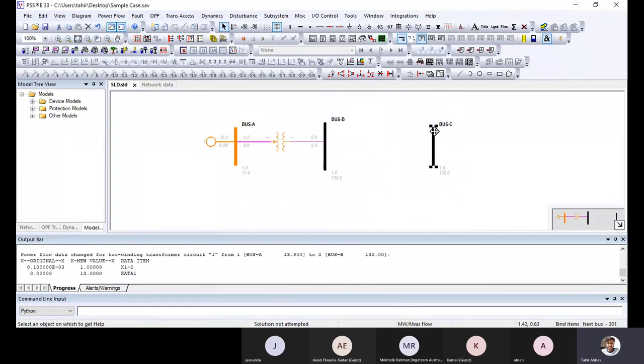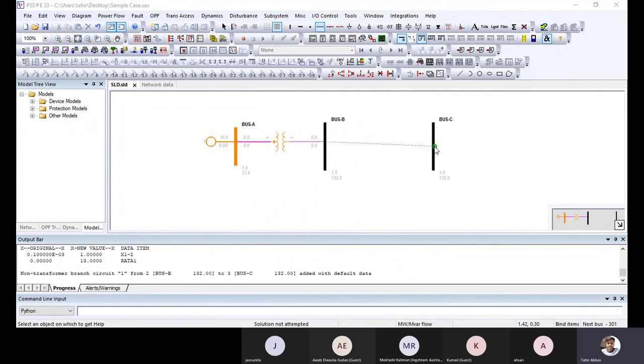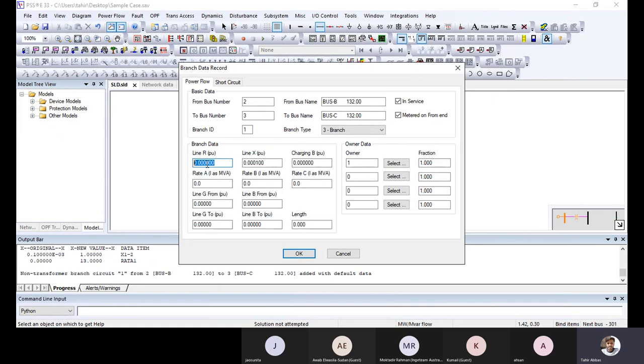Next is the same voltage level, which means there should be a transmission line here, so I'm adding a branch. In the branch, we need to add R in per unit, X in per unit, then the charging value in per unit, then rate A and rate B, the thermal rating, and the length. I'm assuming a zero value, and for the rate, I'm assuming a Linnet conductor, it is 112. The value I can add later, and the length is like 5 kilometers.